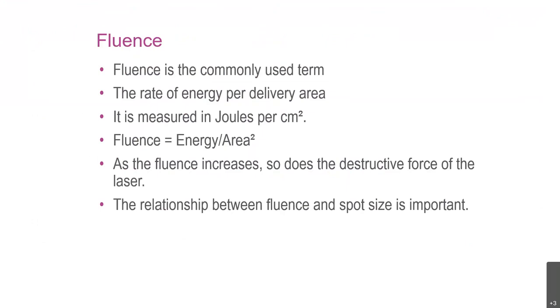The fluence is the energy we're delivering, measured in joules per centimetre squared — we divide the energy by the area we're treating. As we increase the fluence, we increase the destructive force of the laser. If we use the laser at maximum energy, yes, we will destroy our target, but we may start damaging surrounding tissue. We have to get the combination between pulse duration and fluence correct in order to get efficient hair reduction while doing it as safely as possible.